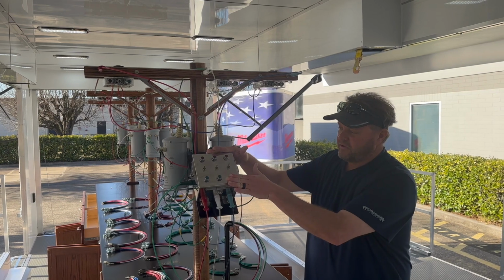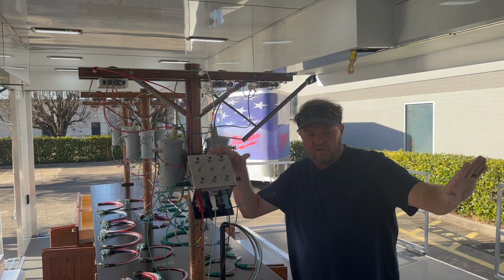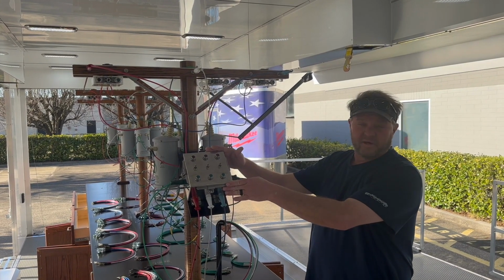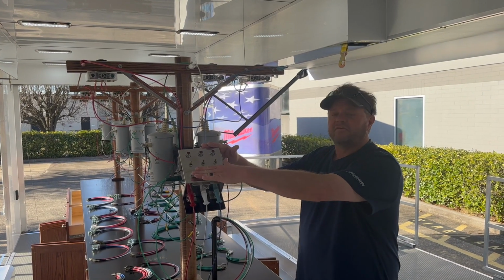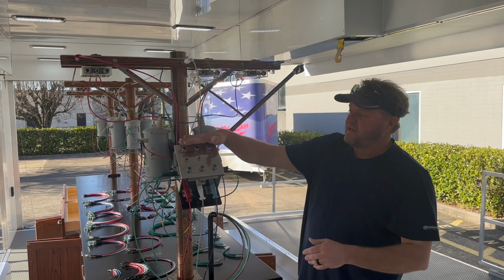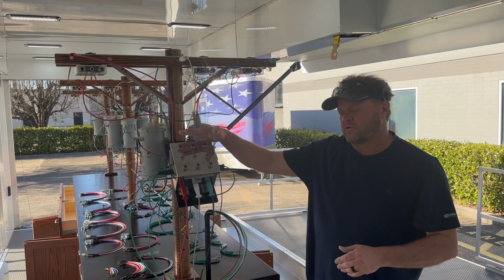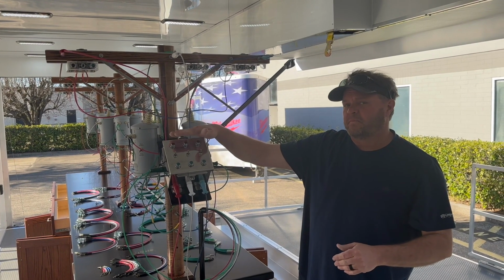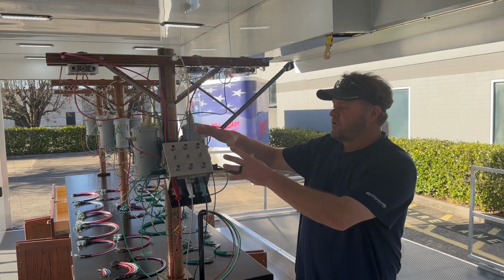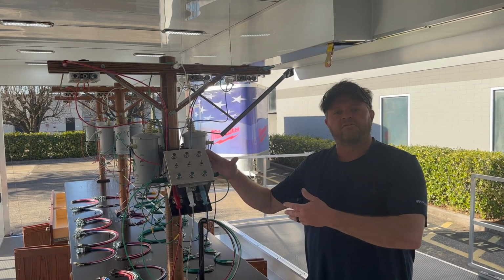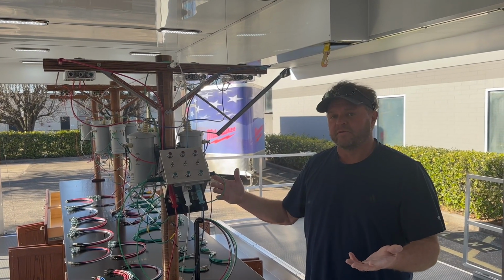The green lights on this mean that there's power, just like all the equipment back here I showed you, we'll talk about it in a minute. The green lights indicate that the equipment has power. The red lights indicate that the breakers are either closed or open and being backfed. So we have indicators on all this equipment at all times, so we know the status of the equipment.